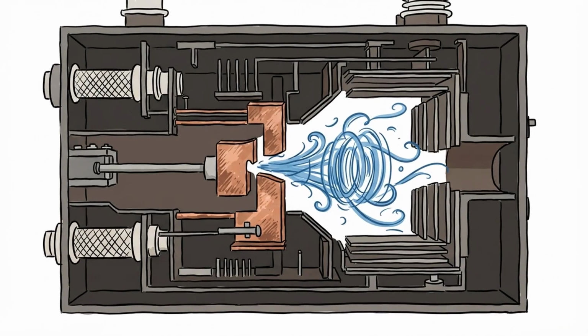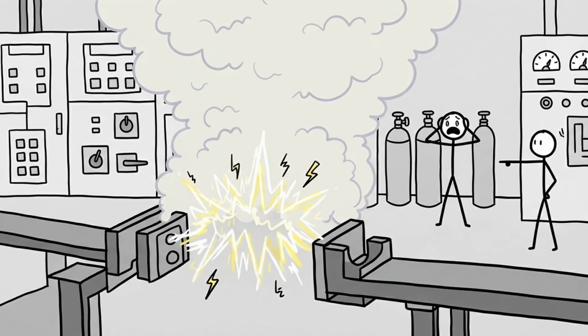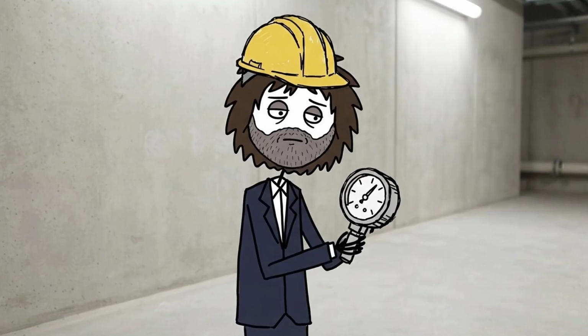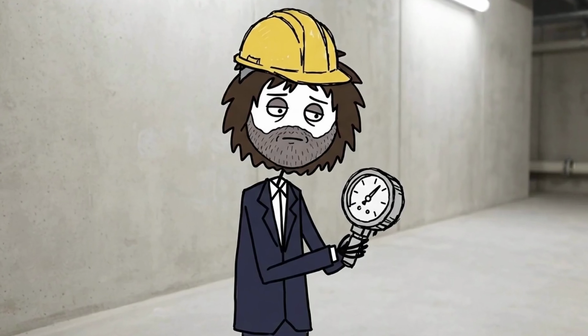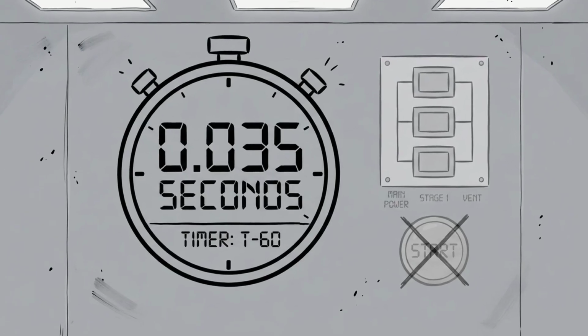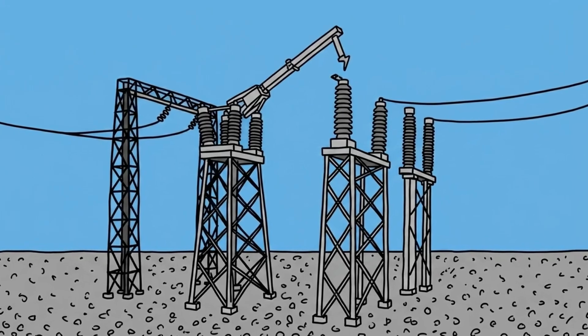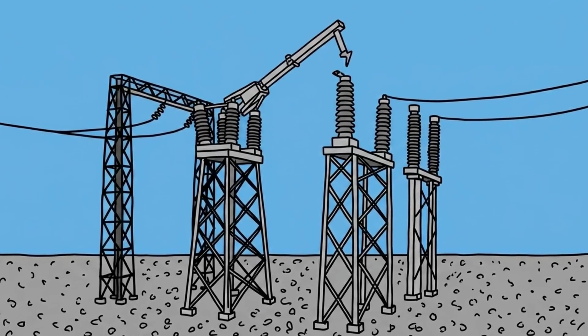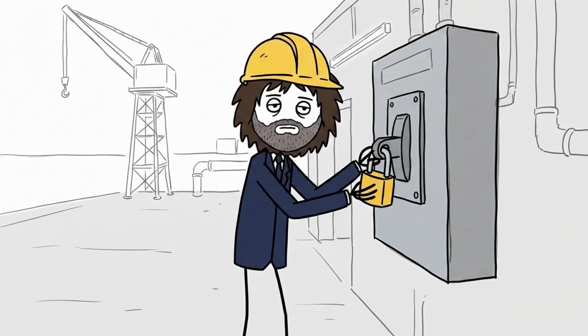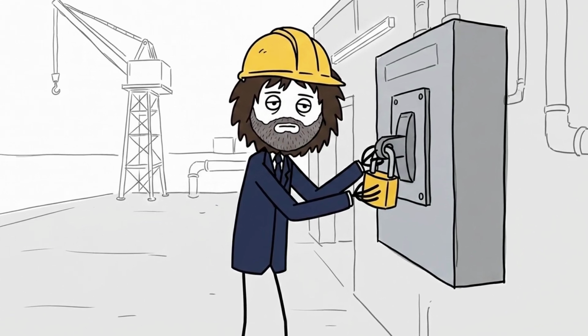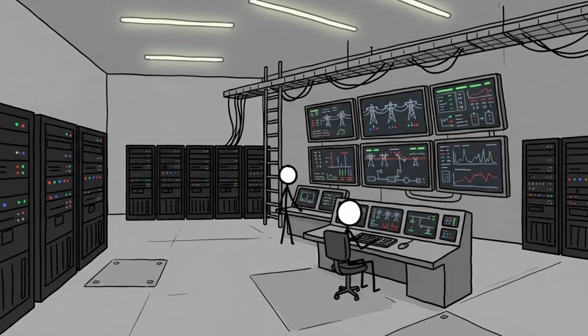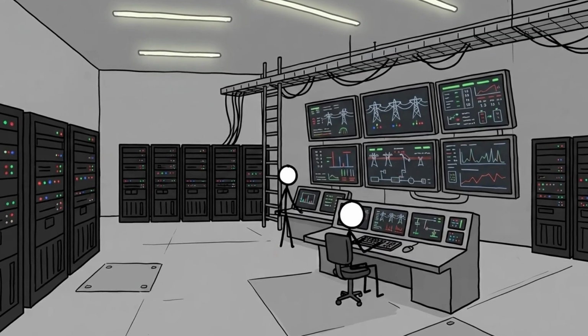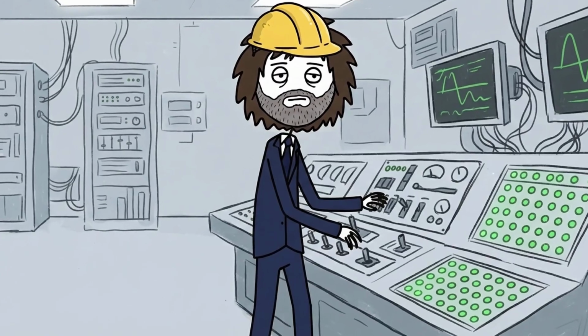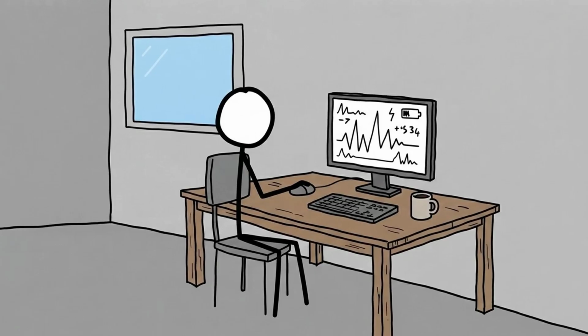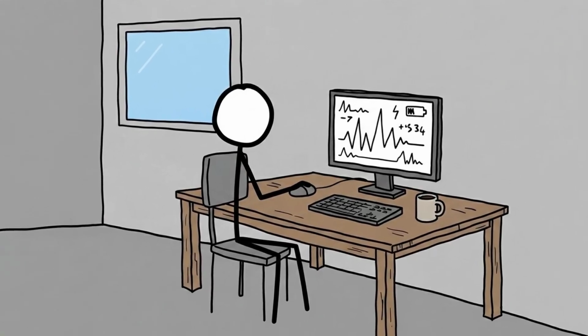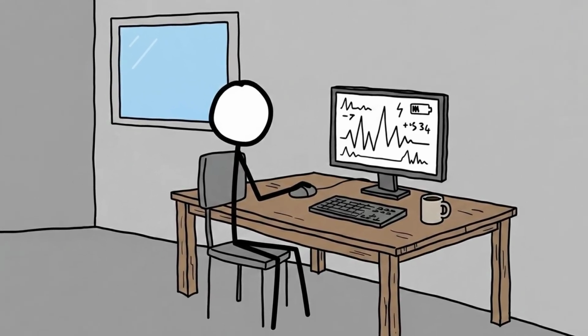To solve this, substations rely on specialized sulfur hexafluoride, or SF6, gas blast circuit breakers. When an emergency fault is detected, high-speed pneumatic springs yank the contacts apart inside a sealed chamber while blasting dense SF6 gas directly across the arc, cooling and quenching the plasma fireball in less than 40 milliseconds before the equipment melts. From the transmission substation, lines branch outward into local distribution substations located right inside your town or neighborhood.